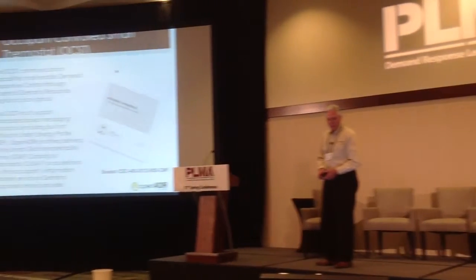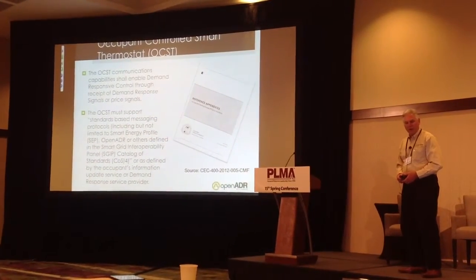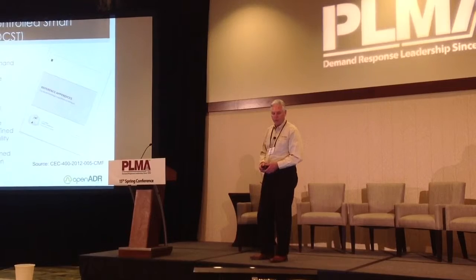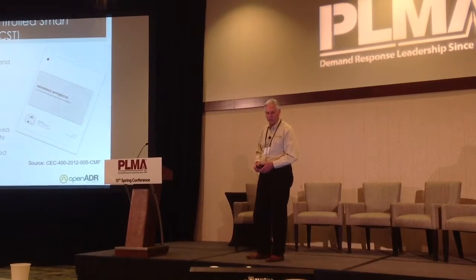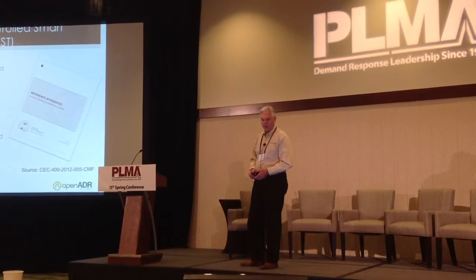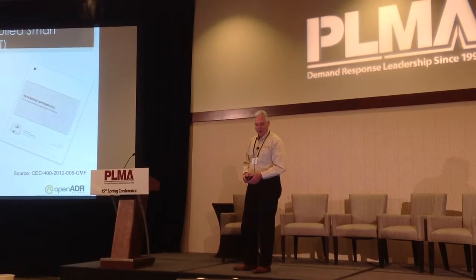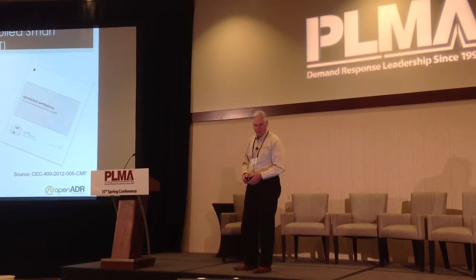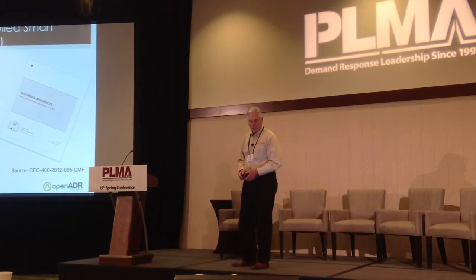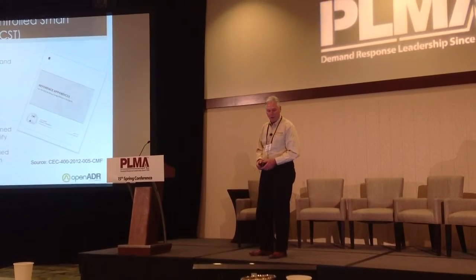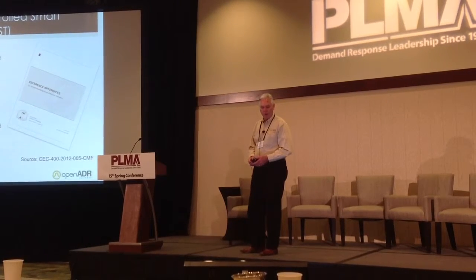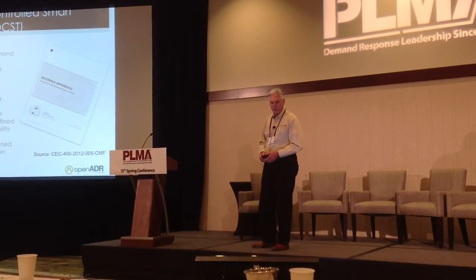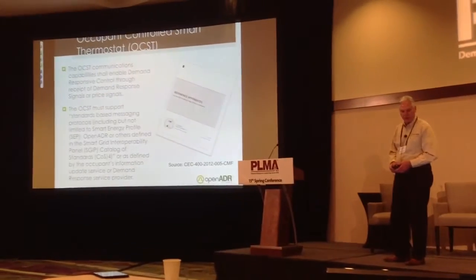For smaller facilities, there's something called an occupant-controlled smart thermostat — what we all call smart thermostats. These are thermostats with a communication interface. The code is more prescriptive here, stating that it must be a standards-based messaging protocol, including but not limited to Smart Energy Profile (SEP), OpenADR, or others defined in the Smart Grid Interoperability Panel (SGIP) Catalog of Standards. Both OpenADR and SEP 2 are now part of that catalog as of last week.